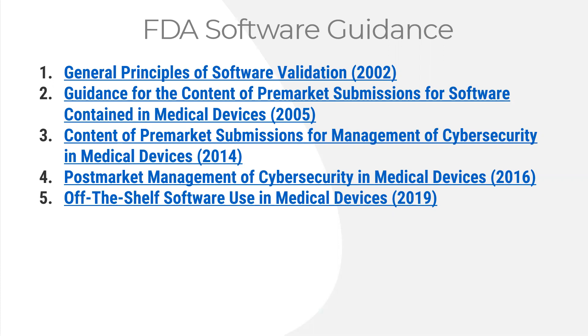The fourth guidance document is the Post-Market Management of Cybersecurity of Medical Devices, a 2016 document. It covers what the FDA expects you to have in a plan for your device after you release it on the market. After approval, you need to monitor cybersecurity of your software operating system and any off-the-shelf software you've used, and in general, track cybersecurity threats and attacks that hackers are trying to use and how they could affect your medical device, prevent it from operating correctly, or cause harm to a person.